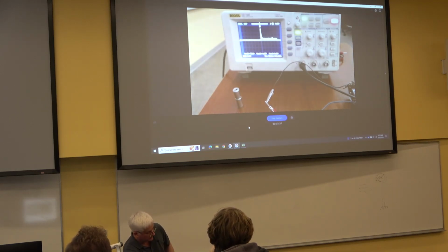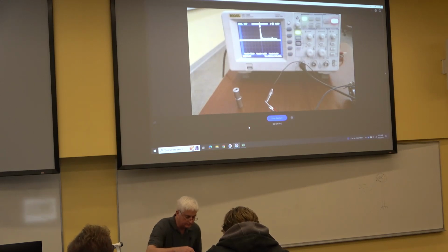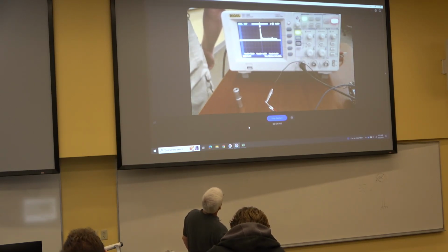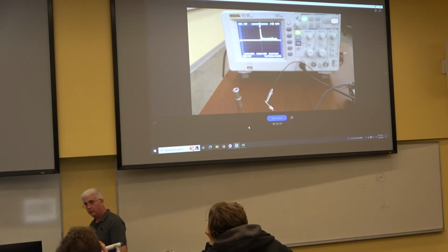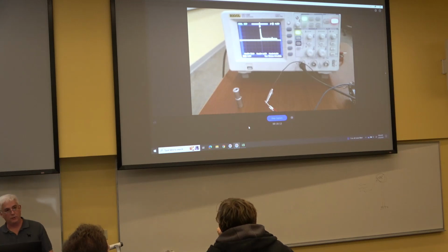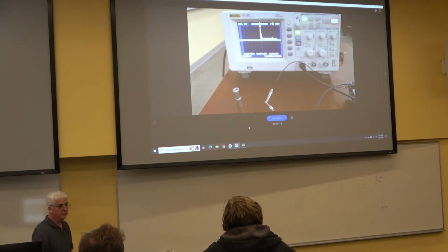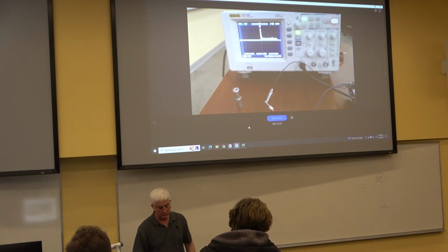All right. So look at that. We've got a big inrush current. When that motor is sitting there with no spinning rotor, it's acting like just a giant piece of wire, right up until everything starts spinning and we get some back EMF. And then that's going to lower your current going through the motor.